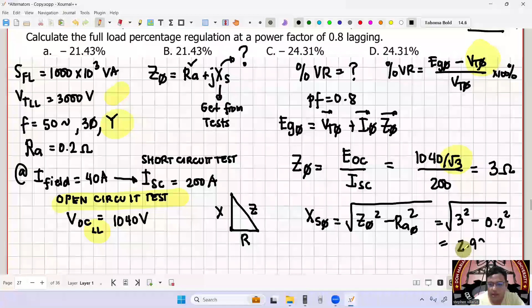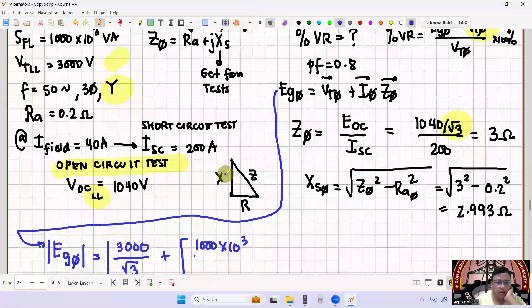So this is now equal to EG per phase. Let's get the magnitude of EG per phase. That is 3,000 over square root of 3, plus our I. Let's get it from S, that is 1,000 times 10 raised to 3 all over square root of 3 multiplied by 3,000 bar angle, our power factor which is lagging, so negative angle, negative arc cosine of 0.8, multiplied by 0.2 plus J2.993.